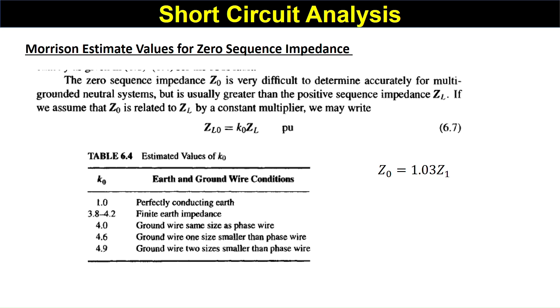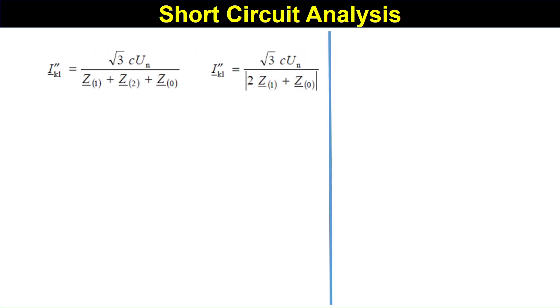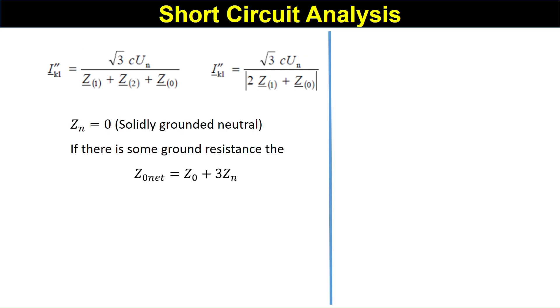From studying various fault and short circuit analyses, we found that the K0 value — meaning Z0 — is generally around 1.03 times Z1, remaining around 1.03 to 1.06. You can choose to use 1.03 or use the table to calculate the zero sequence impedance. In this lecture we will take Z0 equal to 1.03 times Z1. Regarding Z_n, the resistance of the neutral: if the neutral is solidly grounded then Z_n equals zero; if there is a ground resistance, Z0_net becomes Z0 plus three times Z_n. Since we assume solidly grounded, Z_n equals zero.